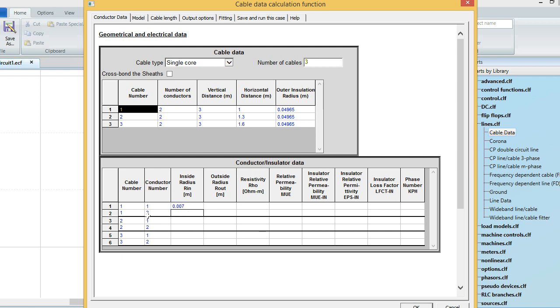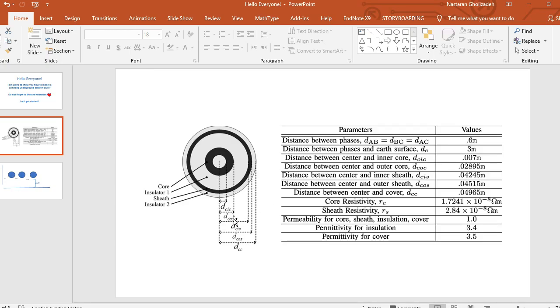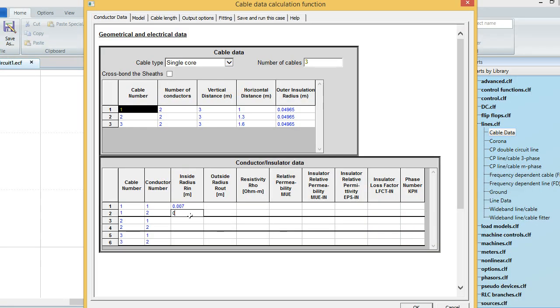The value for the second conductor, which is the sheath, uses the inside radius dcis. The sheath is the black line shown here, and the inside radius value dcis is 0.04245 meters. For the other phases we use the same values, since all phases are identical — so I'll copy this data for the remaining phases.